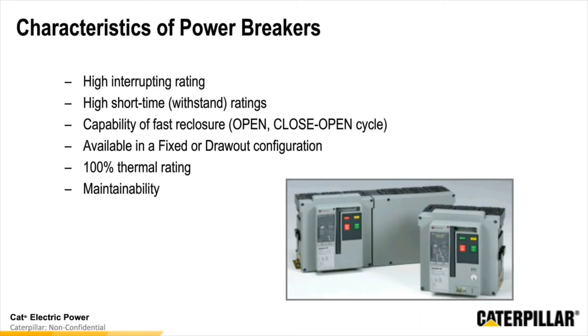And the last breaker is the power breaker. The power breaker is normally a high interrupt rating, so it's typically going to be at the distribution level within the facility. It's also a high short time rating. They're capable of fast reclosures, and they're available in both fixed and draw-out configurations. These breakers are almost always 100% thermal rated, and they're a highly maintainable breaker, meaning that almost all the parts are something that you can take off in the field and do the maintenance in the field, versus having to remove the entire breaker and ship it back.